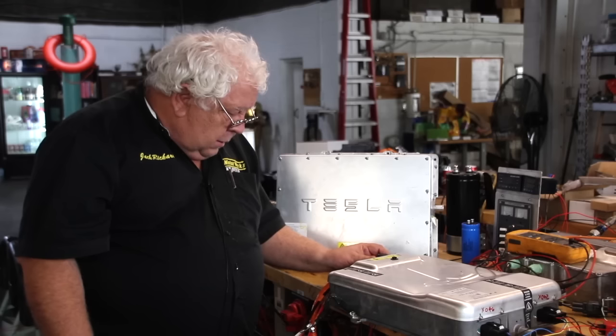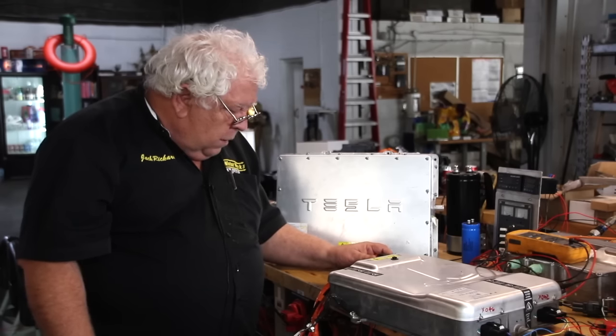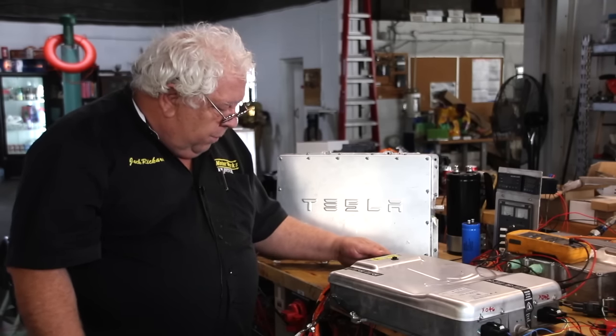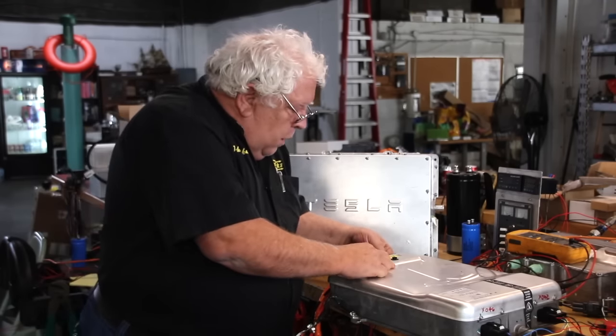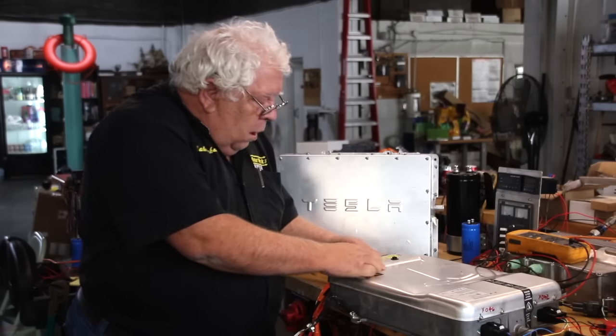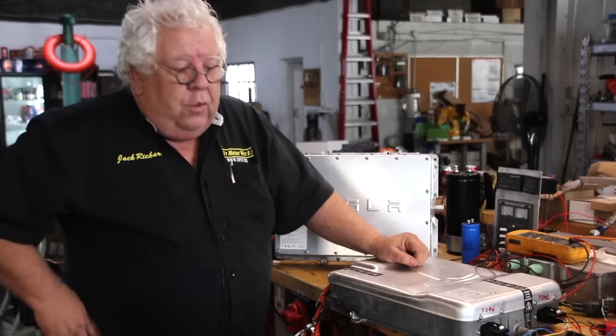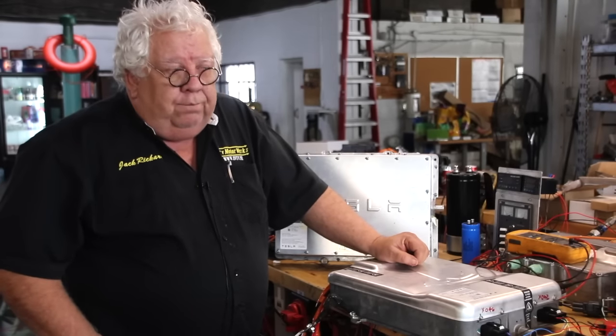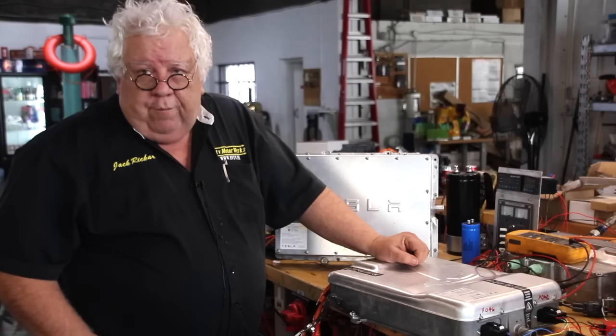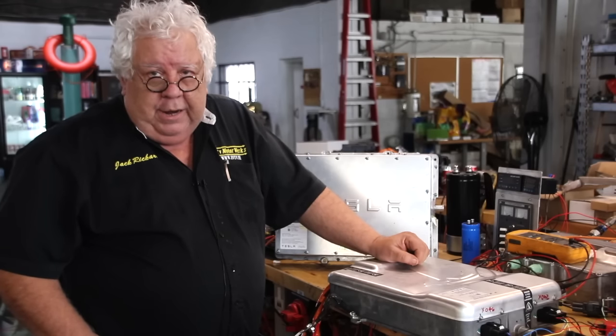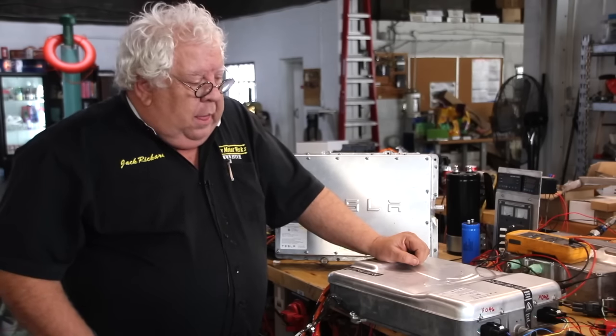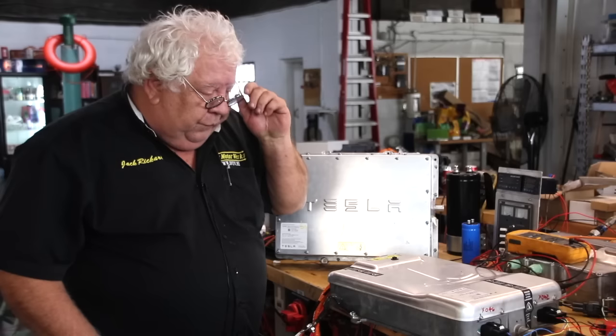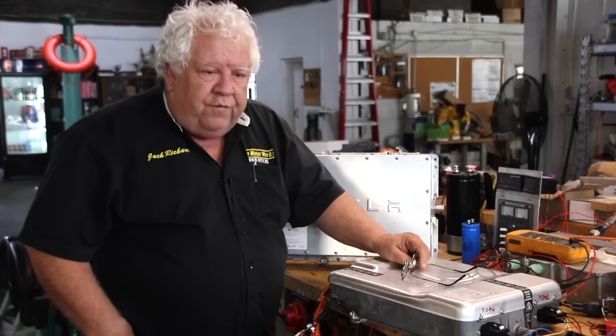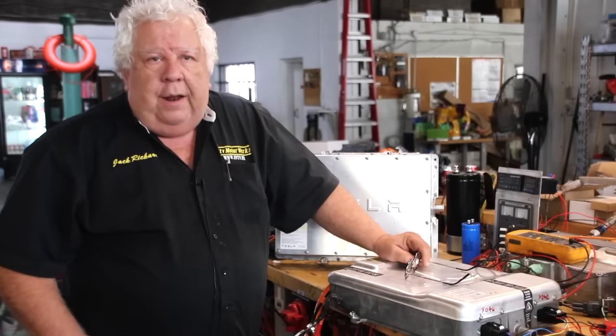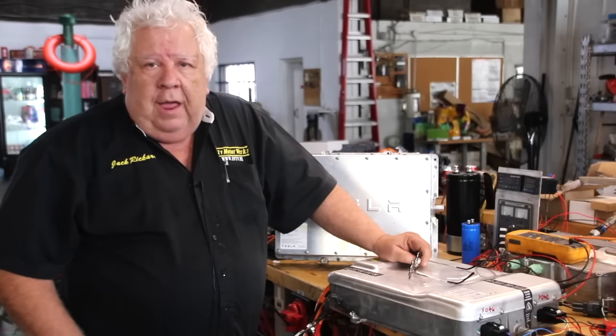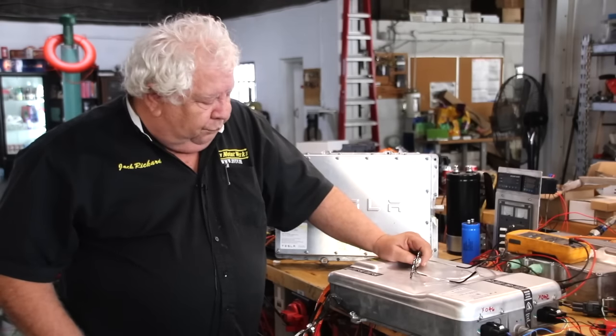power. Now understand, you can hook this up to 3-phase power in Europe, or even plug it into the wall for 120 volts. Here in the U.S., here in the shop, it's 240 volts, but in some areas 208, some areas 220. They call it split phase. It's actually 2 phases, 180 degrees out of phase, and a neutral return.